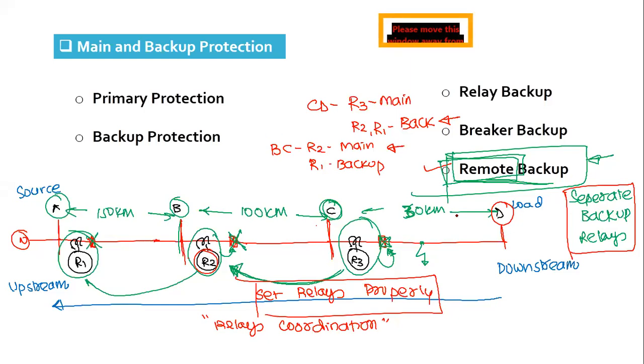Relay backup: all the protective scheme auxiliary equipment is duplicated, very costly, applicable to critical equipment and devices in the system. Breaker backup is if there is a fault on any part of the system, then all the breakers associated with the bus bar of that part are opened. And remote backup is the backup given by the upstream relay in the event the downstream relay fails. Downstream means load side, upstream means source side. Okay, there is some time delay involved, but it is a widely used protection scheme, because here we do not require any separate backup relays in the scheme. So it is not costly at all.